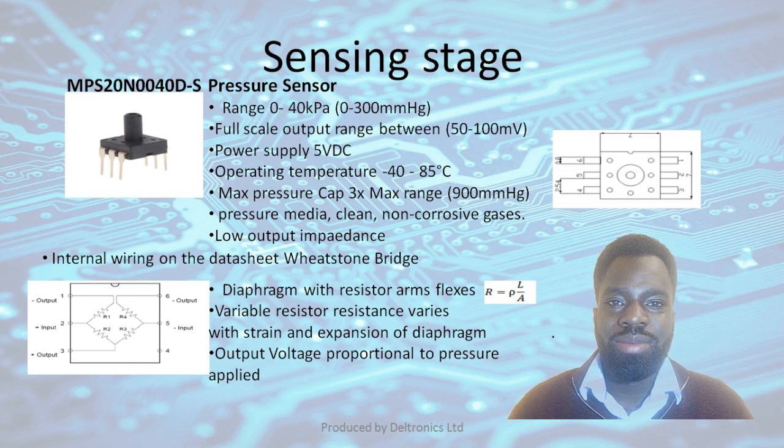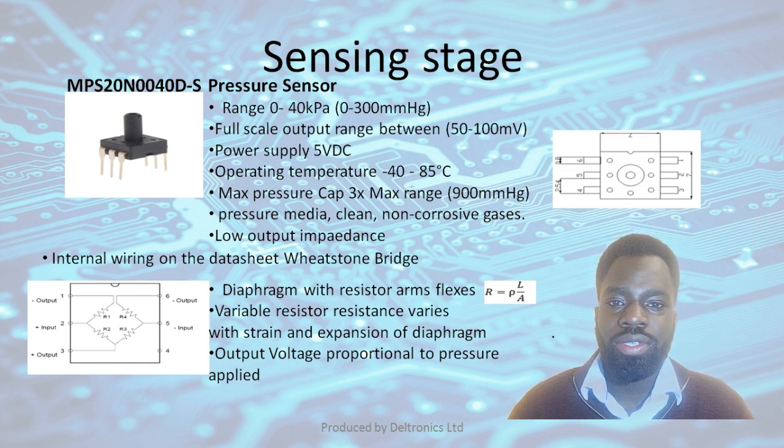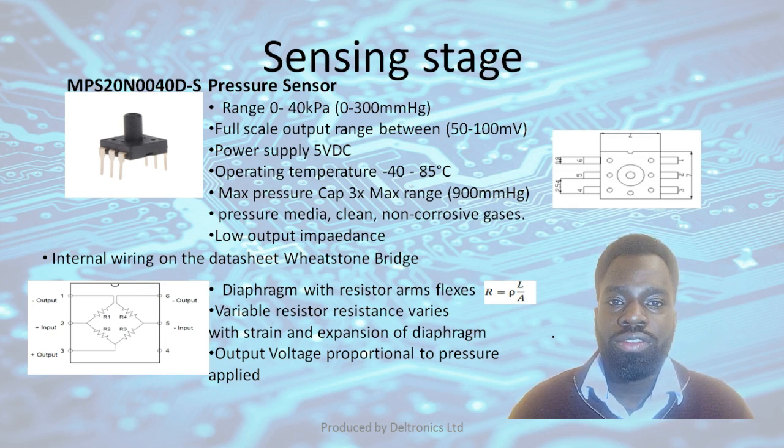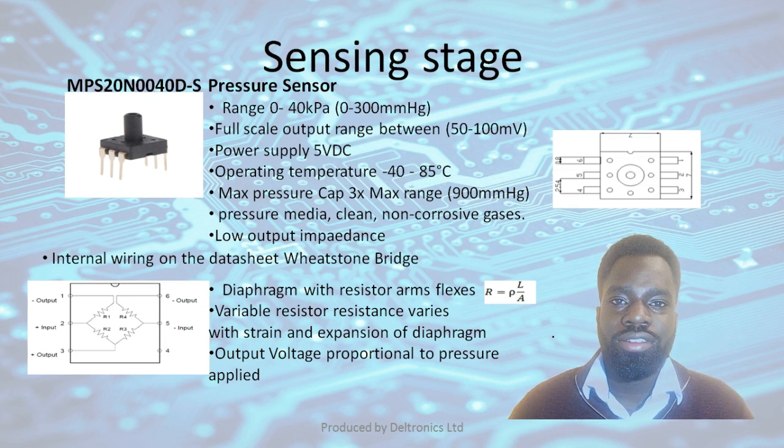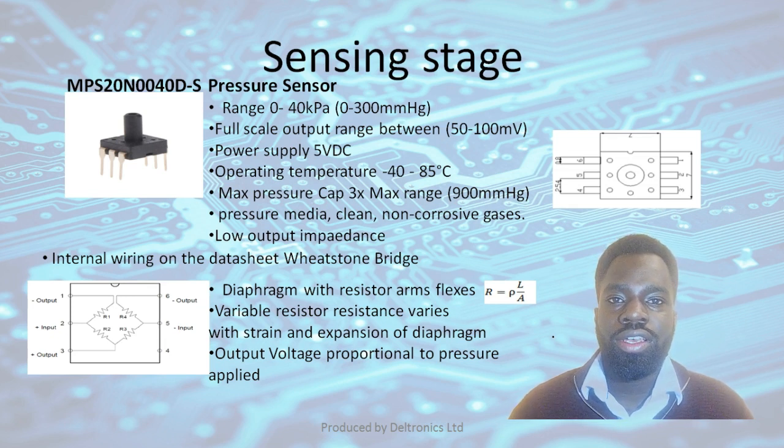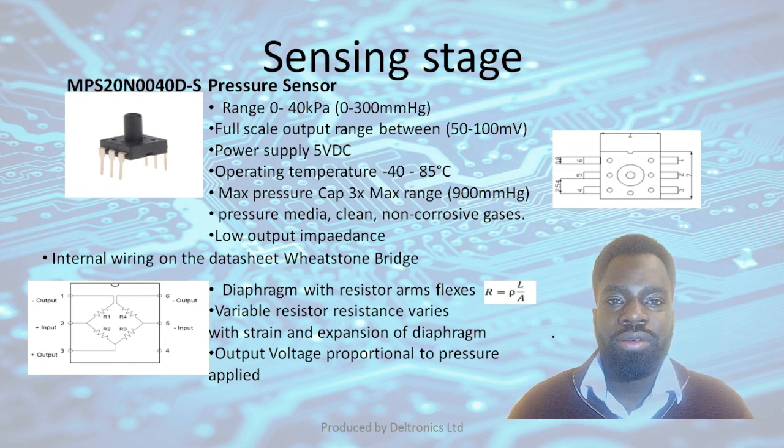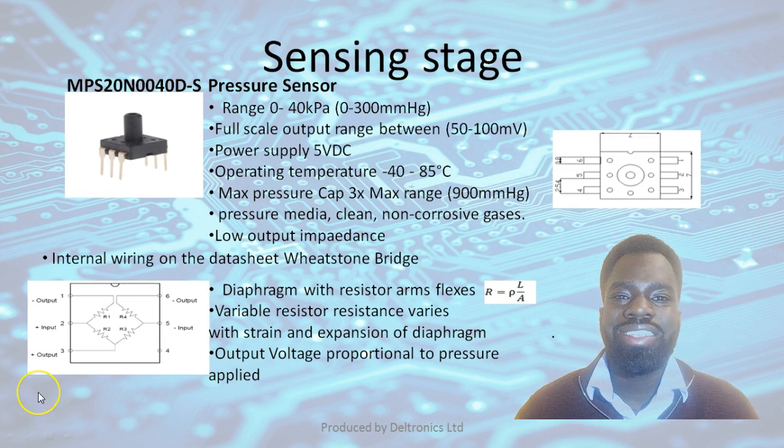The pressure sensor needs to be supplied with 5 volts of stable DC voltage. The pressure sensor accepts clean, non-corrosive gases as pressure medium, such as air, hydrogen, nitrogen, or other non-corrosive gases. Water and other liquids are not permitted to be used on this sensor.